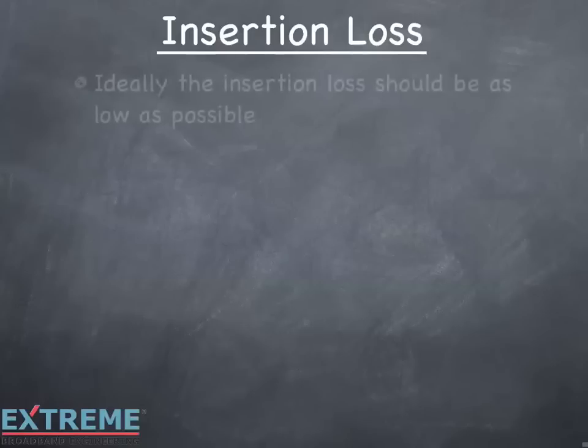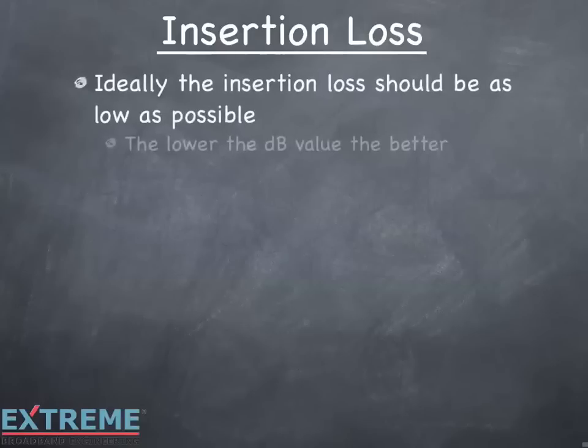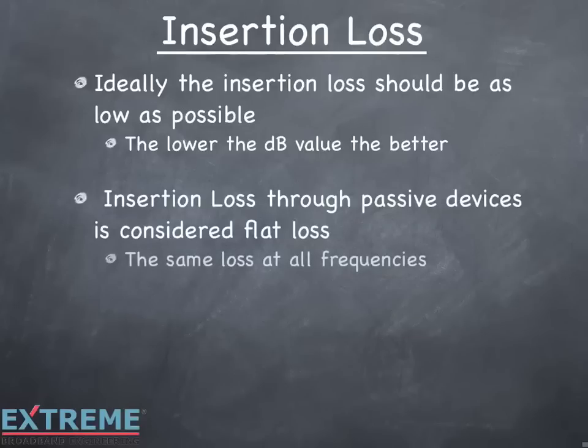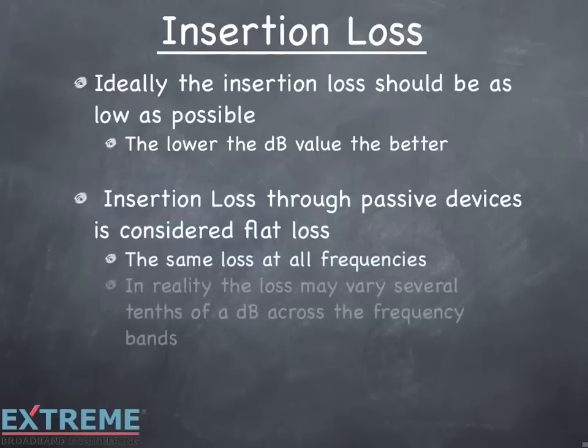Ideally, the insertion loss should be as low as possible — the lower the dB value, the better. The insertion loss through passive devices is considered a flat loss. What we mean by this is that the insertion loss is the same across all frequencies. But in reality, the loss may vary several tenths of a dB across the frequency bands.